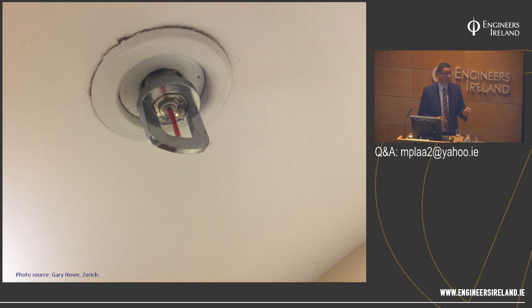So, for example, the BRE at Watford will have a means of testing heads. So if you want the confidence that some heads are actually fit for purpose, both from a will they work, and also you can then ask for the independent fire test data. I do this quite commonly. I ask for testing typically if they've been in the field 5 years, or I don't know the provenance or history of those nozzles, or I've got no data to support them, you can ask for a sample to be sent away for testing.